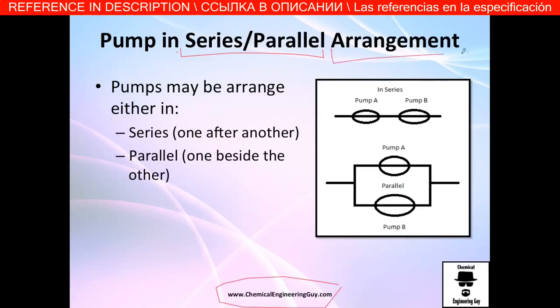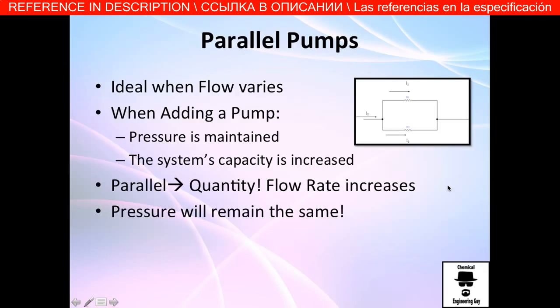So arrangement is essentially how you put the pumps in order to achieve a certain goal, which might be, I don't know, maybe increase pressure, increase head, increase flow rate. We can do this either in series, which is one after another. So here it goes in the inlet, and the outlet of A is the inlet of B, then goes out. Or you can separate the flow rates and work with each separate flow rate, and then you get back. That's the parallel arrangement.